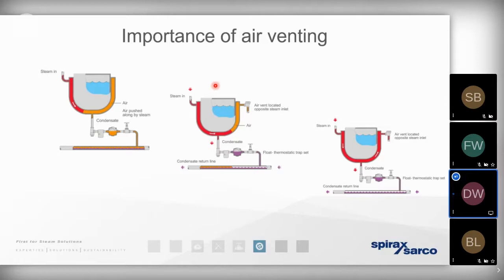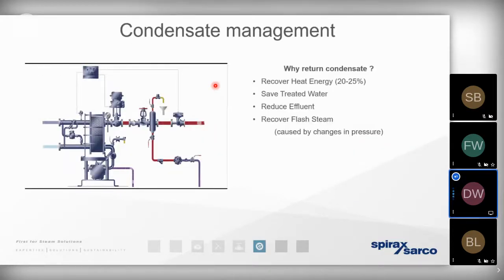So why do we need a steam trap? Why don't we just let that condensate pass straight out of the solution and be dumped to waste? Well, there are a number of different reasons. The first and most obvious reason is that not only would we be losing the condensate, but we would be losing a significant mass of steam to atmosphere.